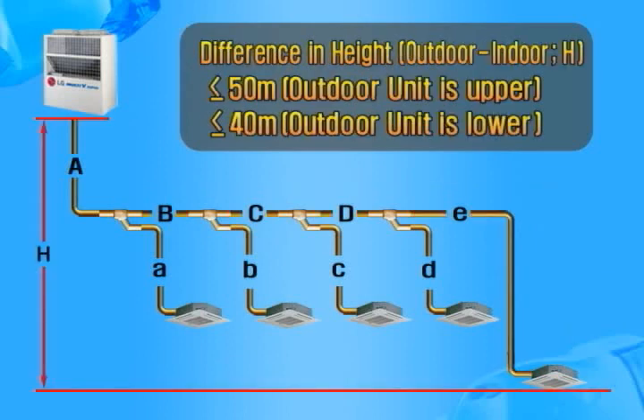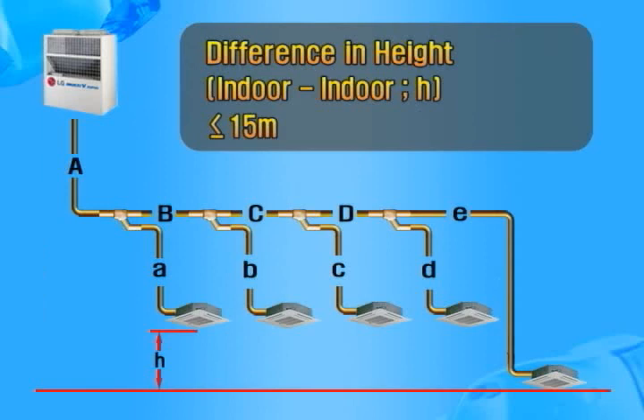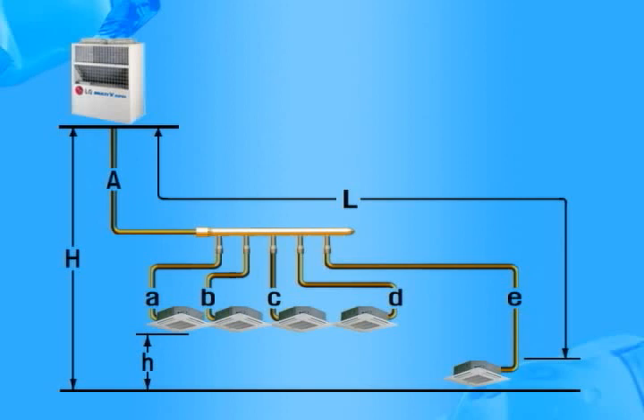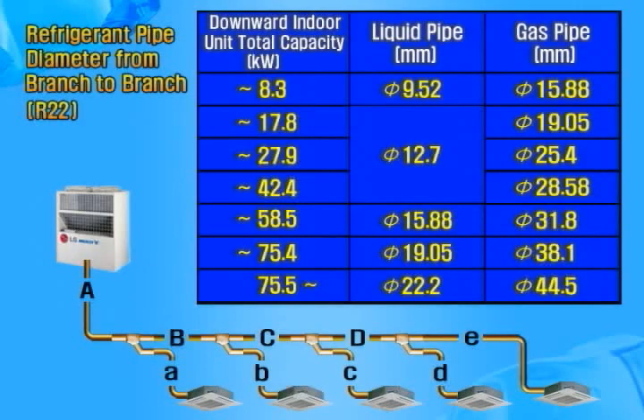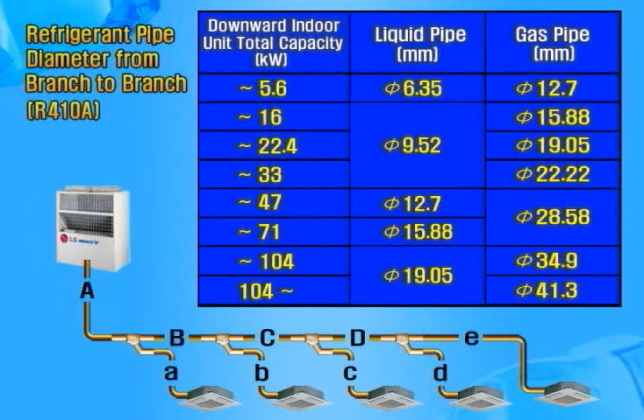The height difference between indoor units and outdoor units should be within 50 meters if the outdoor units are higher, and 40 meters if the indoor units are higher. The height difference between indoor units is within 15 meters. The first branch, A, should have the same diameter as the service valve. Each refrigerant pipe B, C, and D has different diameters for liquid and gas pipes depending on the total capacity of the indoor units.